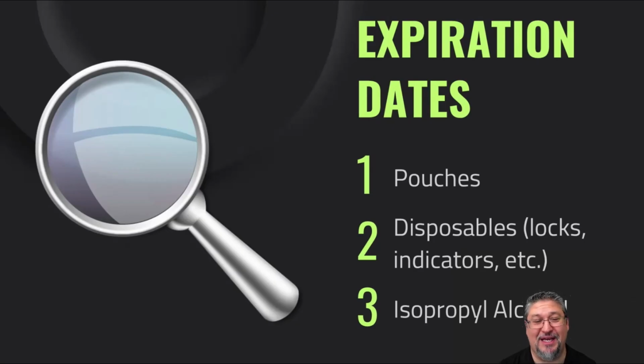The disposables like locks and indicators, especially those color change locks and indicators, should have an expiration date. And if you dump them out of their packaging or their box, a lot of them do not have expiration dates on the indicators themselves. Now, the indicators, like the class 5 integrating indicators, some of those will have the expiration date or the manufacturer date on the back side. But a lot of the locks and those kinds of things don't. So if you're dumping them into a secondary container, make sure that you keep the right lot number and that the box or container you're using to hold it is labeled with the correct expiration date, and make sure that you have some type of documentation that shows that you are looking at those things and changing them out when needed.